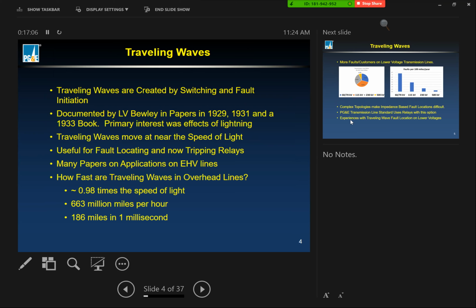So traveling wave and fault location has been used for a long time in certain specific applications. Even communication lines, they've used some of that, but they'll come out and connect some temporary portable test equipment, run different frequencies, and look at the reflected energy from those different frequencies to try to determine how far out a buried telecom line has a fault. So traveling waves move near the speed of light, useful for fault locating, and now for some tripping relays.